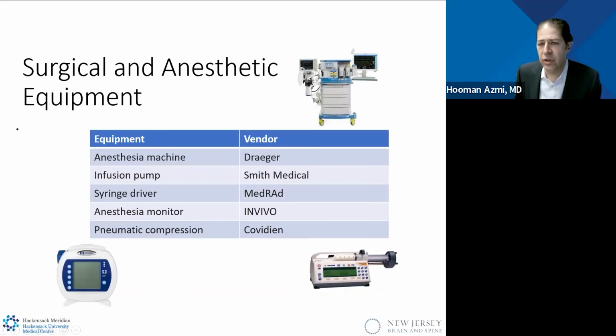So what we use is an MR compatible anesthesia machine. This is our vendor; there are many vendors out there. We have an infusion pump that the anesthesiologists use that is MRI compatible. They choose to leave it outside and bring the tubes in through the waveguide, but this is capable of being used inside the 5 gauss line.